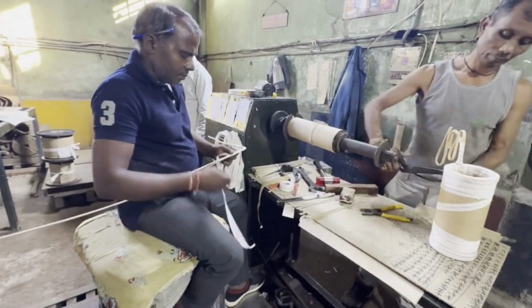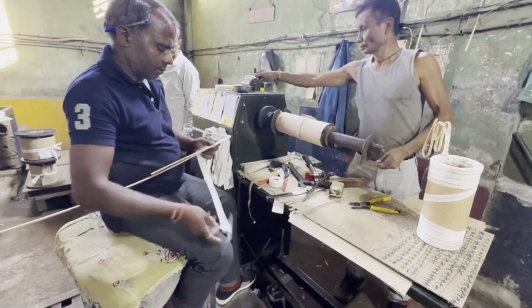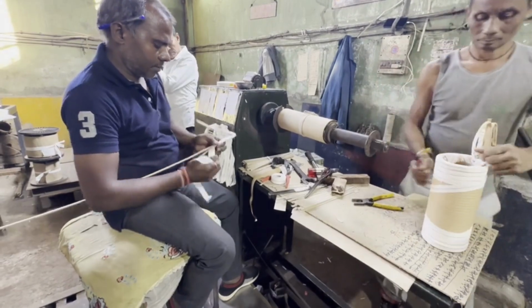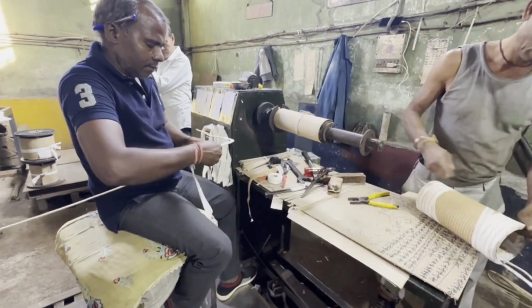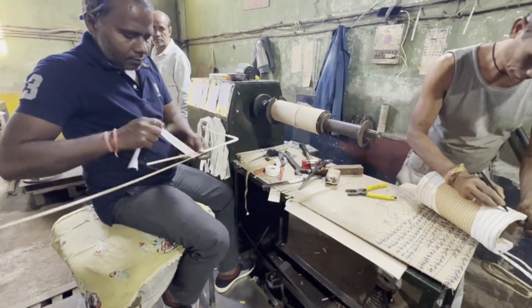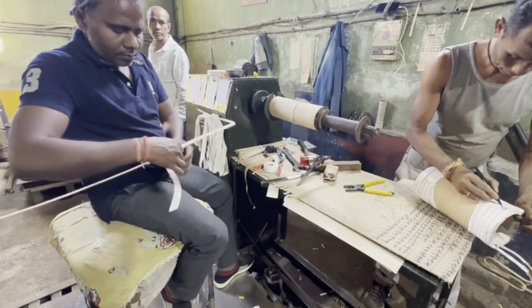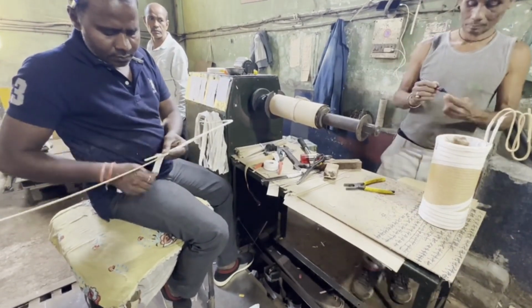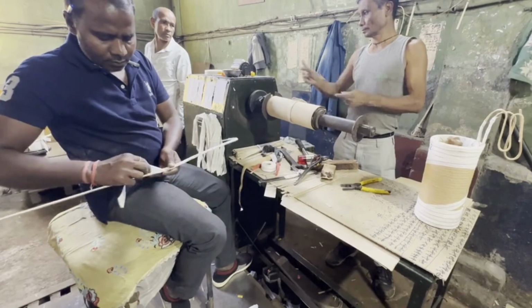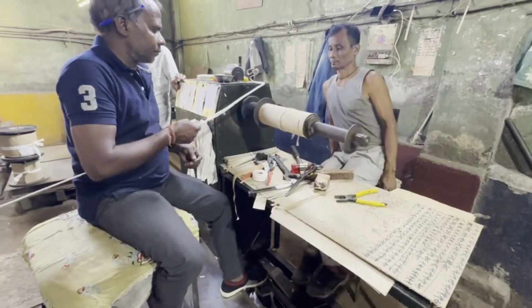Notice the paper insulation between turns. That thin layer prevents internal short circuits. At the ends, cotton taping is applied for mechanical strength and protection. Watch the tension control. Too tight, insulation damage. Too loose, movement during fault current.